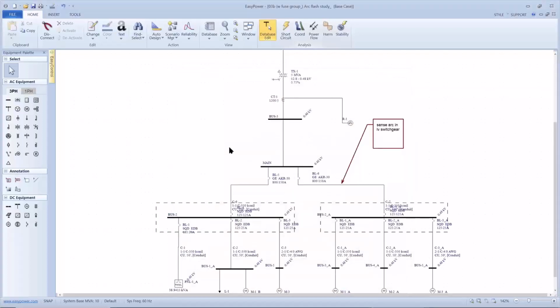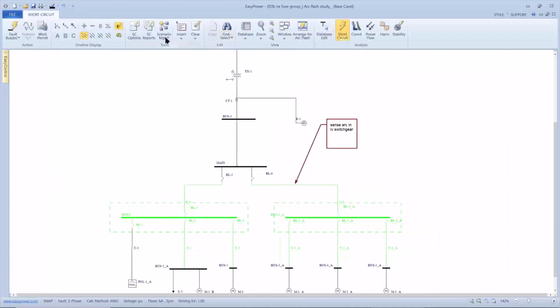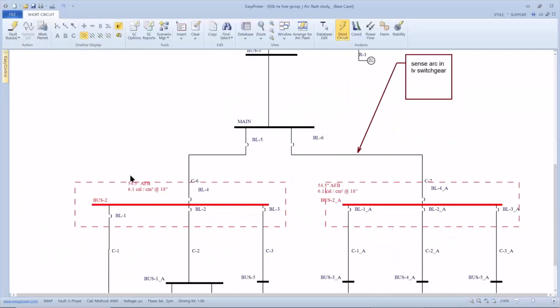So now when I go into looking at arc flash, wherever my sensors are placed, if I look at my arc results, I get less than 8 calories, which wouldn't be available if I just had breaker protection down below. Robert's saying, note, healthcare uses an NFPA 99 that does not coordinate up to 1/10 of a second. Thanks, good to know.